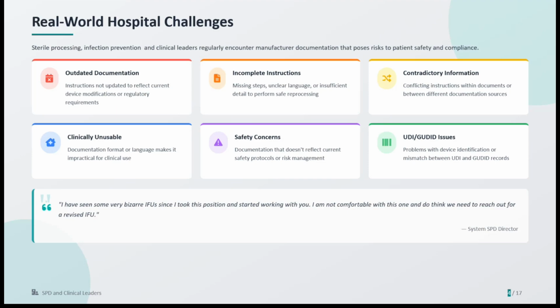People often ask, are manufacturers penalized for this? And unfortunately, there isn't a strong direct penalty structure solely for a bad IFU, but that doesn't mean we accept them as is. Together as hospitals and partners, we hold manufacturers accountable by identifying the gaps, documenting them, and requesting corrected, validated instructions. And in all the work we've done, there have only been a small handful of manufacturers, literally just a few, that consistently resist making correction. The vast majority will fix documentation when we anchor the discussion in FDA and ISO requirements, and of course, staff satisfaction and patient safety.